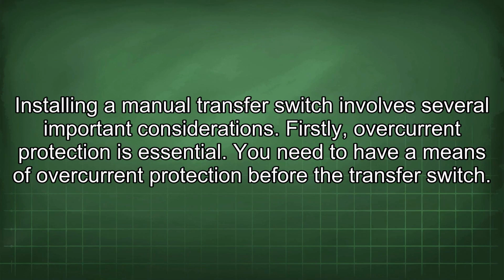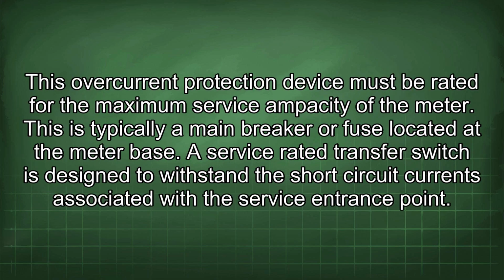Installing a manual transfer switch involves several important considerations. Firstly, overcurrent protection is essential. You need to have a means of overcurrent protection before the transfer switch. This overcurrent protection device must be rated for the maximum service ampacity of the meter. This is typically a main breaker or fuse located at the meter base.